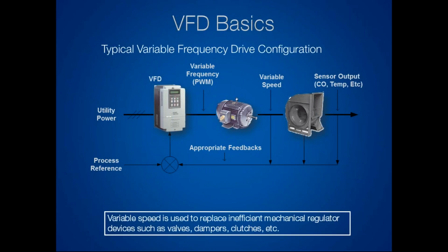Okay, so let's think of an example. Let's think of just the temperature in a room. Let's say it gets up to 72 degrees in the room. We want our air conditioner to kick on in that room, but as it progressively gets warmer, we want that air conditioner to work harder and harder, right? So that thermostat is telling our VFD exactly what the temperature is, and then that VFD is responding with the appropriate amount of airflow in order to cool that room down, okay? Go ahead and move to the next slide.